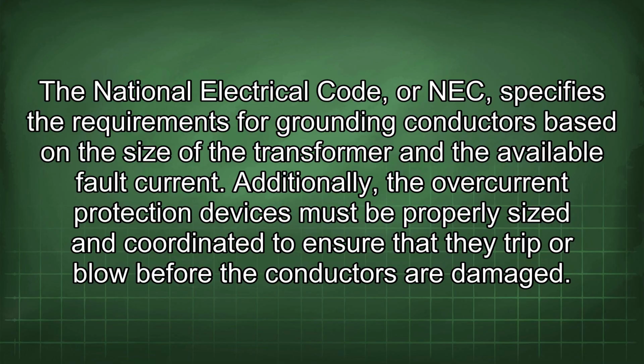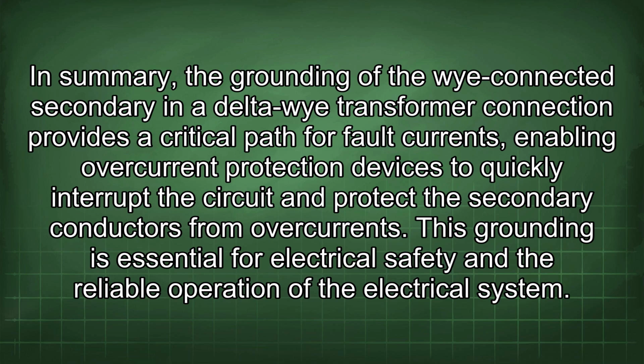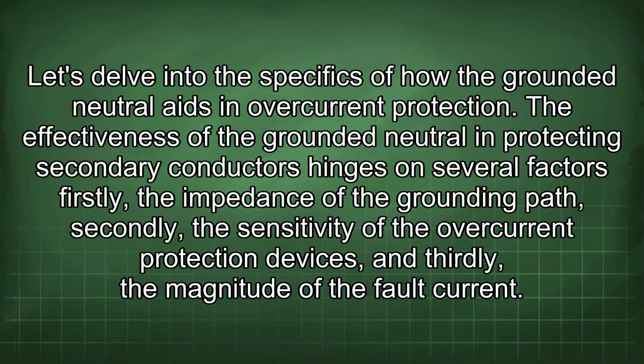Additionally, the overcurrent protection devices must be properly sized and coordinated to ensure that they trip or blow before the conductors are damaged. In summary, the grounding of the Y-connected secondary in a Delta-Wye transformer connection provides a critical path for fault currents, enabling overcurrent protection devices to quickly interrupt the circuit and protect the secondary conductors from overcurrents. This grounding is essential for electrical safety and the reliable operation of the electrical system. Let's delve into the specifics of how the grounded neutral aids in overcurrent protection.